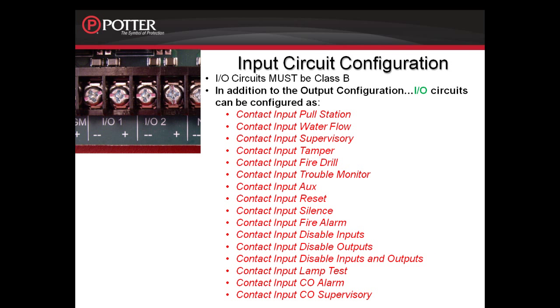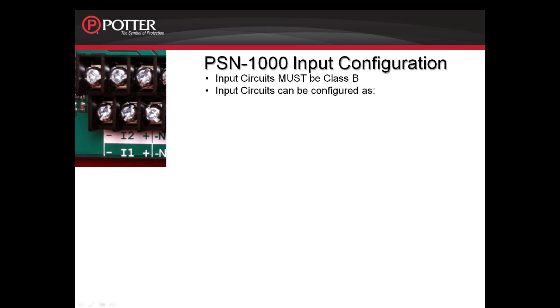Remember, each I/O circuit can be configured individually. If additional input circuits are required, you can install a PSN-1000 smart power supply that gives you two additional input circuits. The two input circuits on the PSN-1000 also must be wired Class B, and they have the same configuration list as the I/O circuits on the input side.